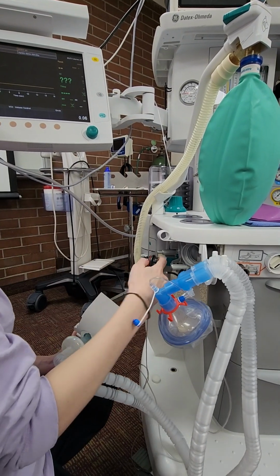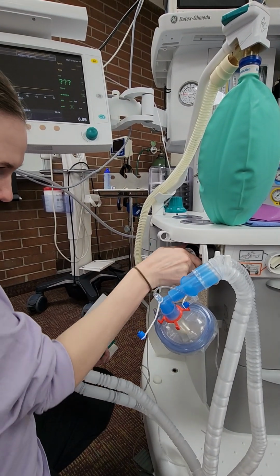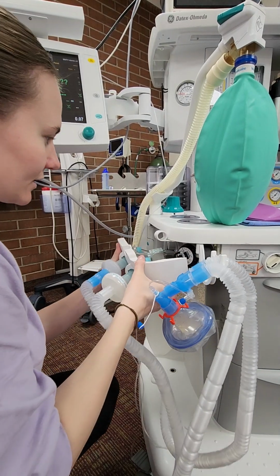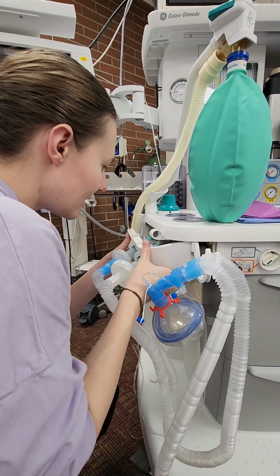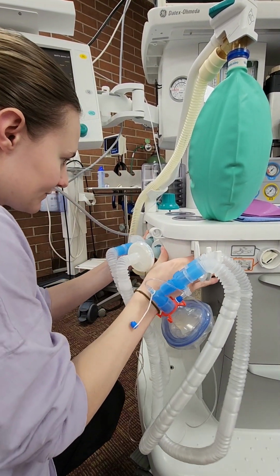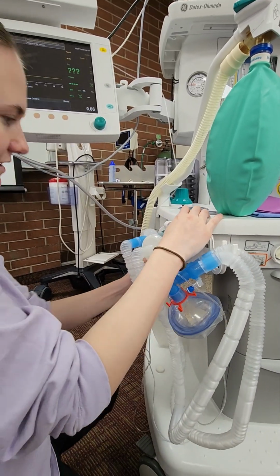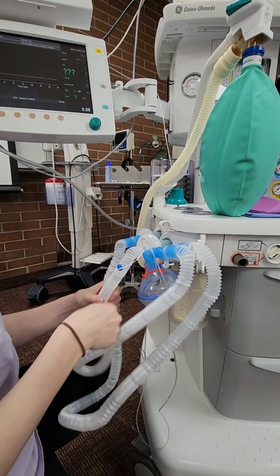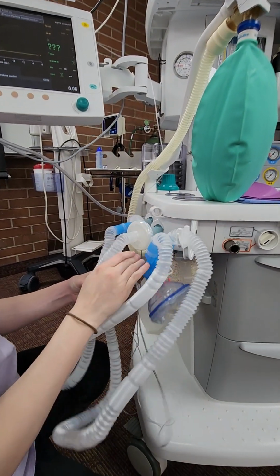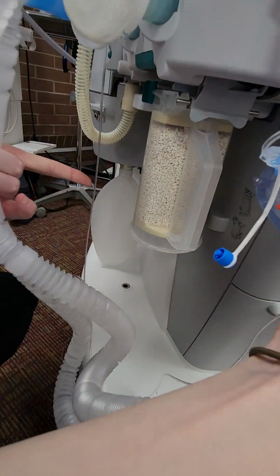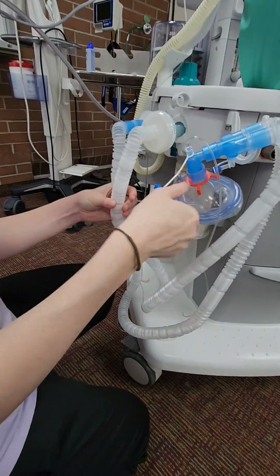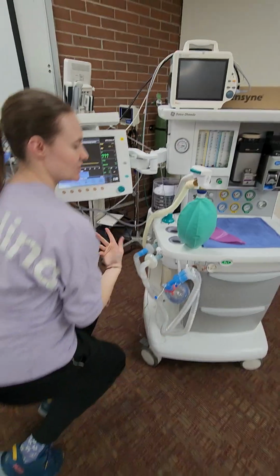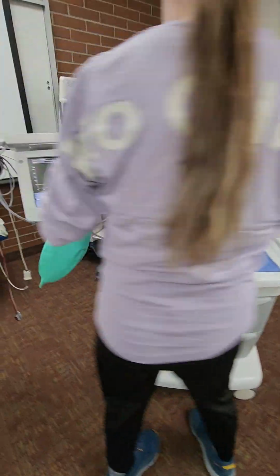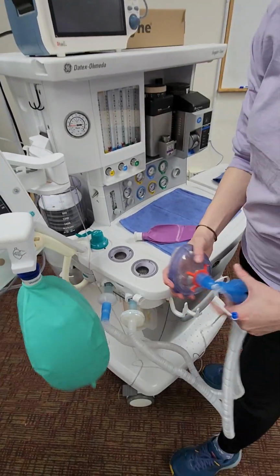Once it's done, you'll screw it back in securely and put your cassette back in and secure it with this lever. You can also check your CO2 absorber down here to make sure that it's not purple and that it's an acceptable level of purple. If you need to change it, you can change it. So now you will check your high pressure leak test.